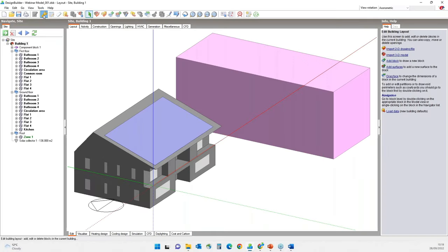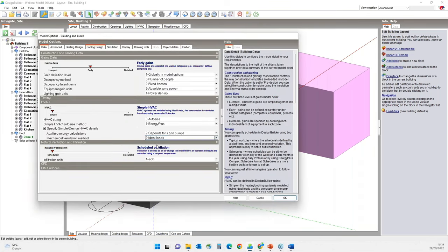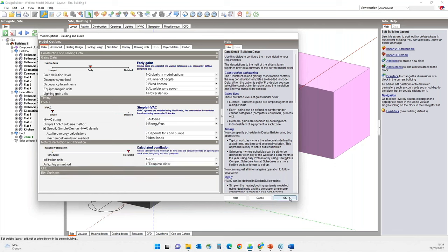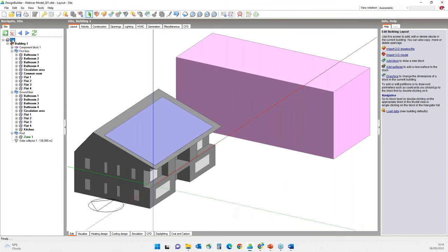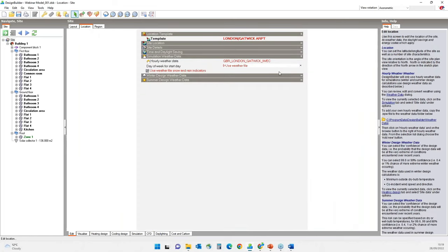For detailed natural ventilation analysis, you can switch from scheduled to calculated option in the model options. Once you have set the required model option inputs, you should ensure that the correct weather file is loaded, as this depends on the analysis you are carrying out. For example, some analysis only needs to represent typical building operations using a typical meteorological year weather file, whereas TM59 analysis would require a design summer year weather file. For this webinar, I will leave it as it is.